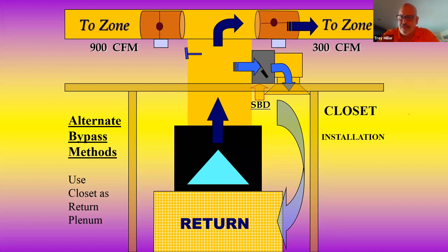How did I eliminate the sweating? I conditioned the closet. Now, this is not something you want to do with a gas furnace because the inspector will look at you like you lost your mind because of combustion air. But if we're dealing with a heat pump or maybe a 90% furnace with a concentric duct kit, you could work with this. But this is a great application, especially in tight closets when we don't have any return ductwork to tie into.